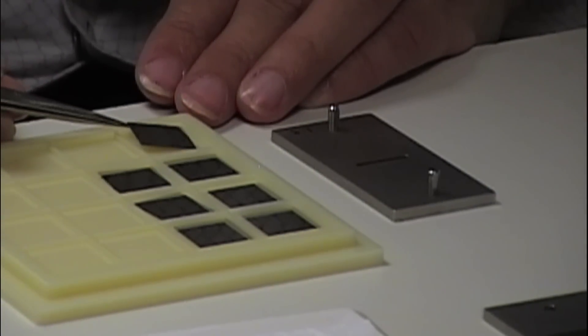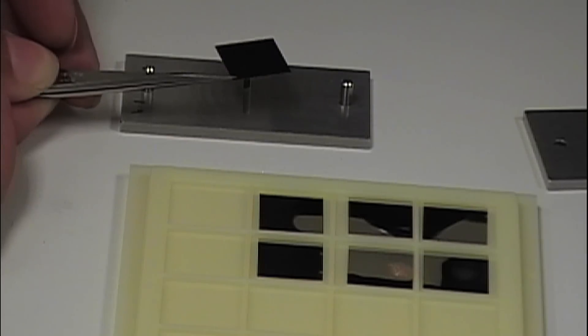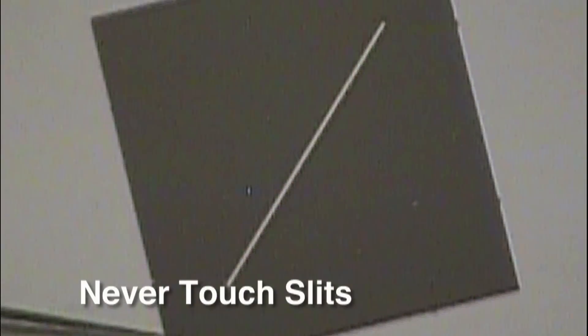The slit and pinhole aperture substrates are very thin and extremely fragile. Any physical contact will likely damage them. Treat the slits with care. Never touch them with anything.